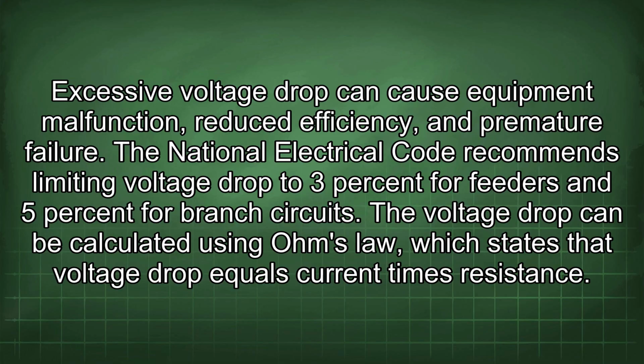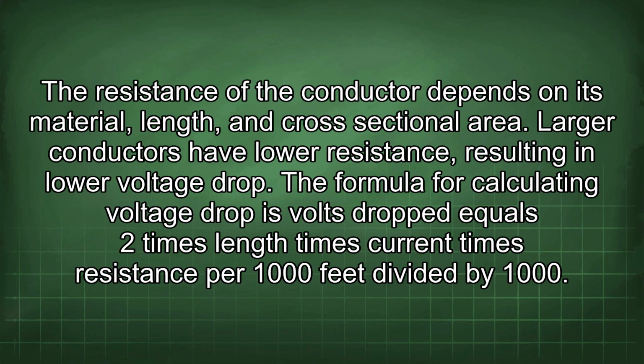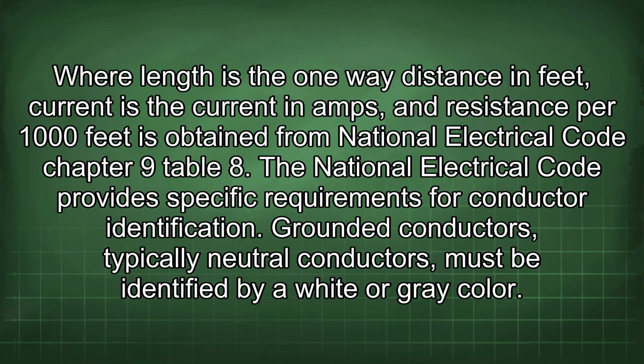The voltage drop can be calculated using Ohm's law, which states that voltage drop equals current times resistance. The resistance of the conductor depends on its material, length, and cross-sectional area. Larger conductors have lower resistance, resulting in lower voltage drop. The formula for calculating voltage drop is volts dropped equals 2 times length times current times resistance per 1000 feet, divided by 1000. Where length is the one-way distance in feet, current is the current in amps, and resistance per 1000 feet is obtained from National Electrical Code Chapter 9, Table 8.